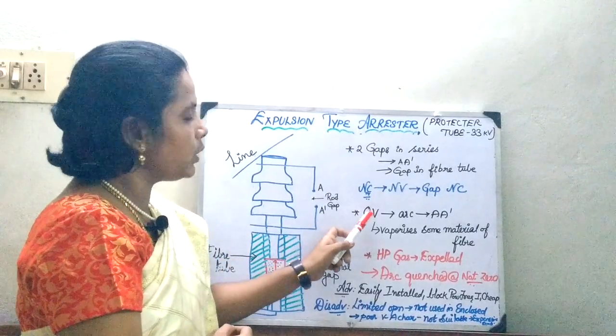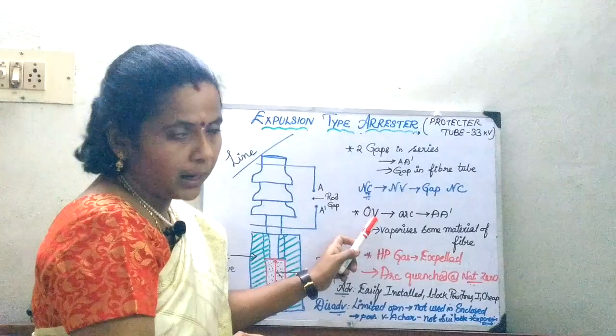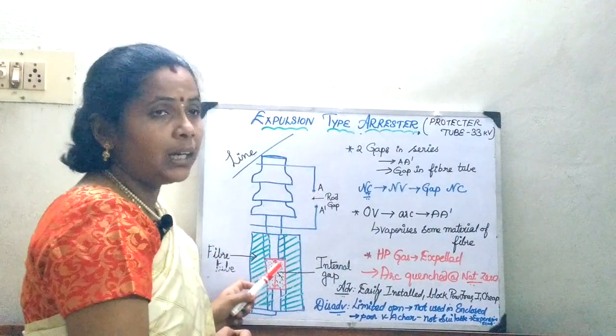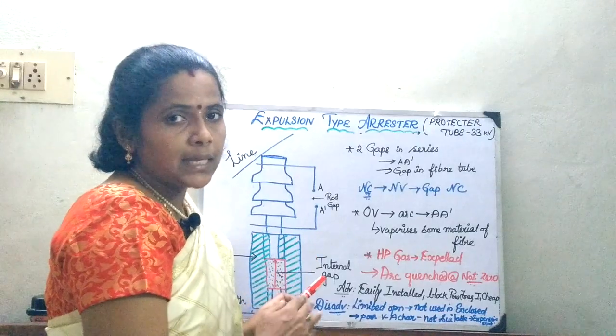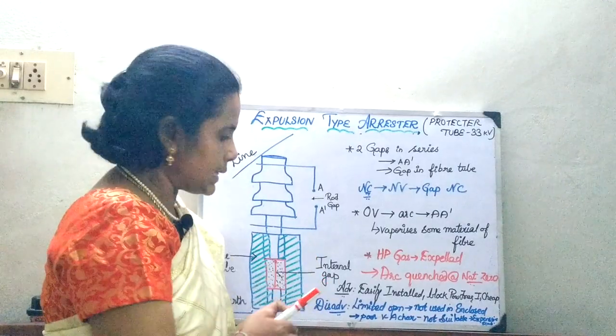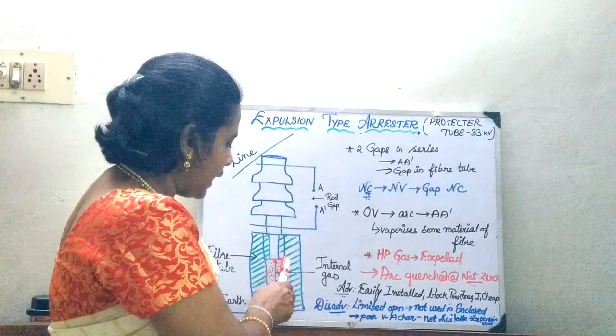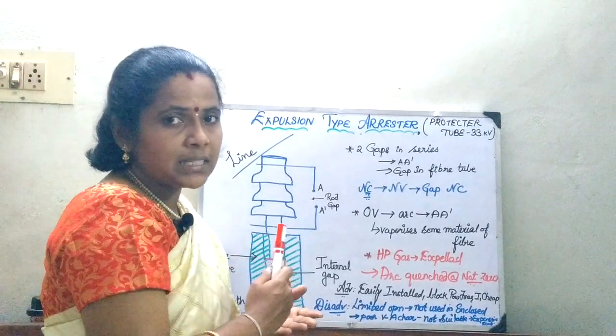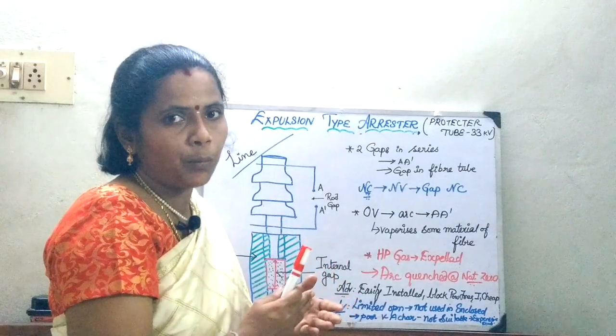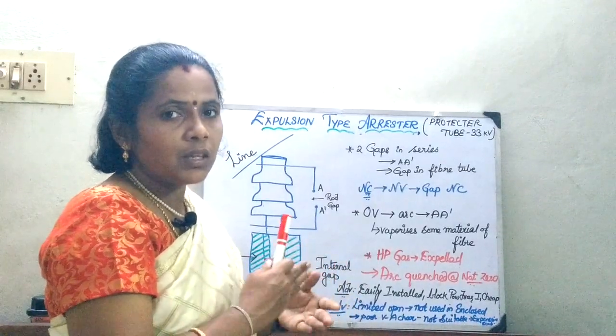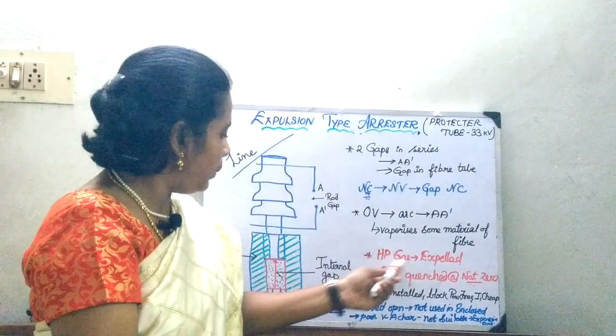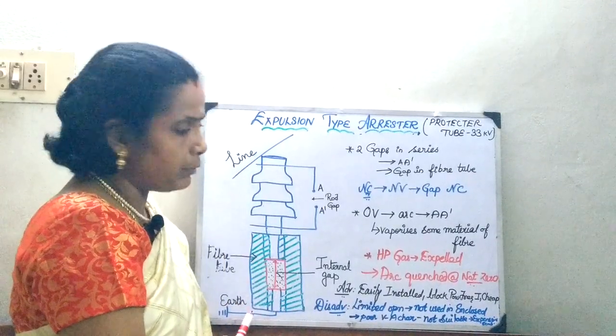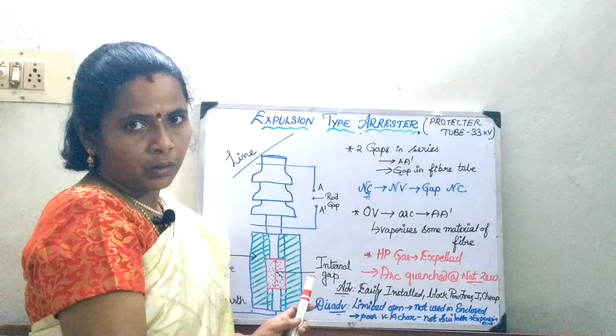What happens whenever the over voltage is going to penetrate - after the series arcing of this path, here also it is going to start arcing. So, in that case, it will vaporize some of the gases inside the layers of your fiber material. As a result, after some time, there is going to be a high buildup of pressure. So, this high pressure gas will be expelled outside through the hollow part of the lower electrode.